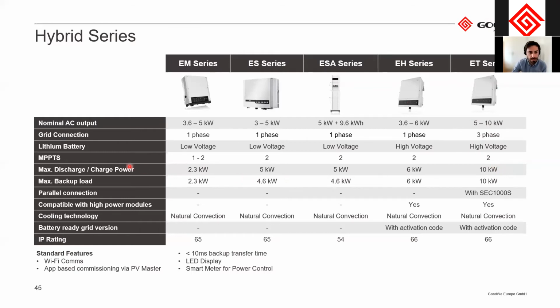and what's here is the backup load and the max discharge power. This is a function that all of our hybrid inverters have, that they have a backup function. And as you see, most of them can output as much power in backup mode as they do in on-grid mode. The only difference here is the EM inverter that has slightly less backup power. Also, you see most of them have an IP rating of 65. The only exception is the ESA, which is the tower with the batteries, and it's because the batteries don't have the IP65 rating.